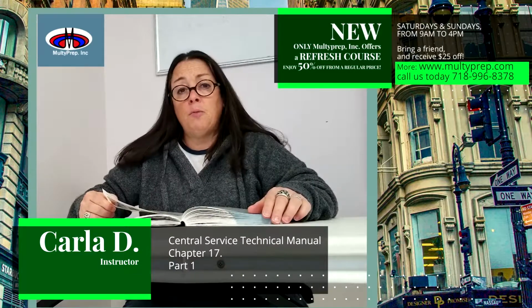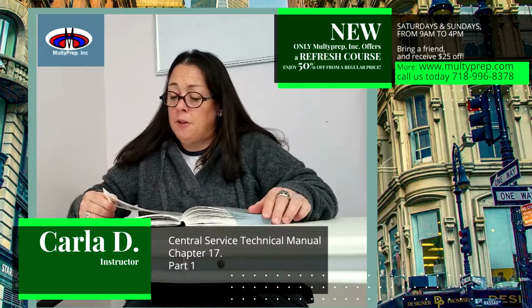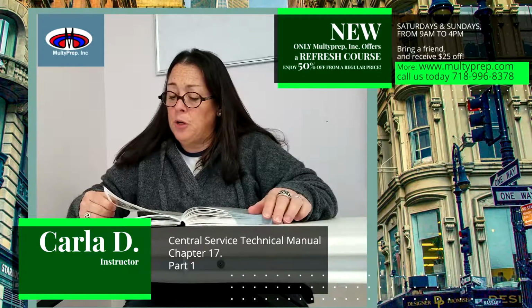Some facilities use CIs that consist of heat-sensitive dye applied to a cardboard strip or a dye that moves along a window. When exposed to a sterilant, these devices gradually change color, thereby integrating a time component to the measurement. Physical monitoring. Physical monitors include time, temperature, and pressure recorders, displays, digital printouts, and gauges. See Figure 17.7.